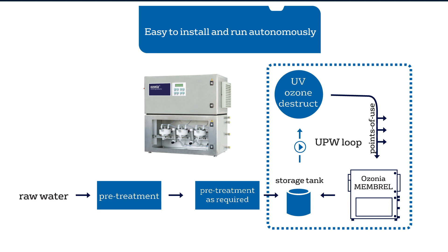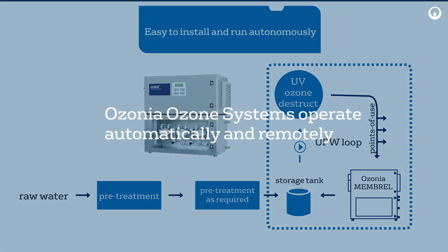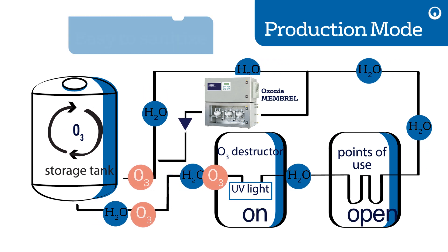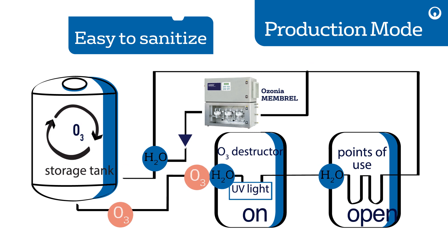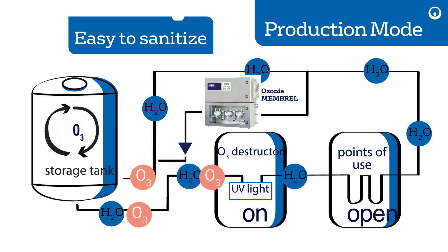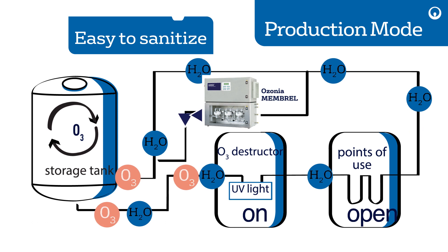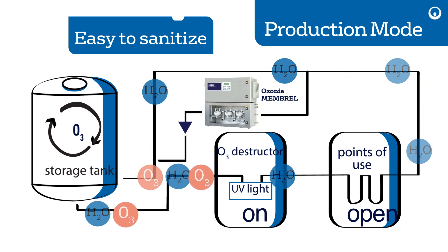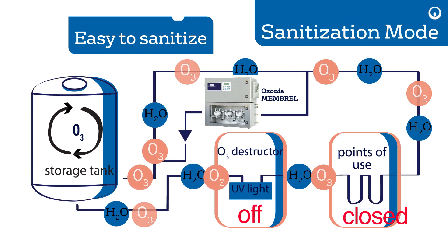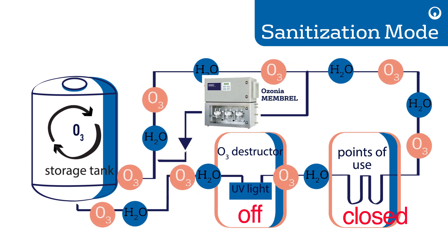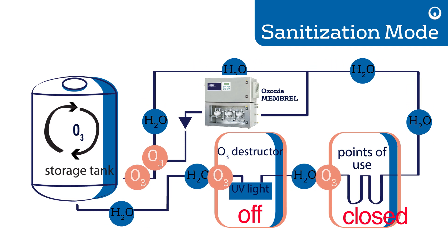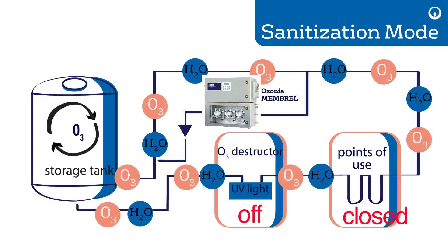Ozonia ozone systems operate automatically and remotely. In normal production mode, ozone is utilized to continuously sanitize the majority of the ultrapure loop, and an inline UV removes the ozone just ahead of production. For complete system cleaning, switching to sanitization mode turns off the inline UV and ozone is allowed to contact the entire system. Returning to production is as easy as turning back on the ozone destructor.